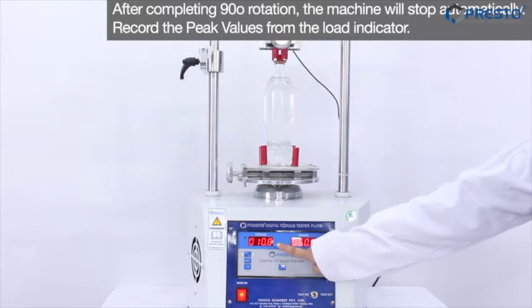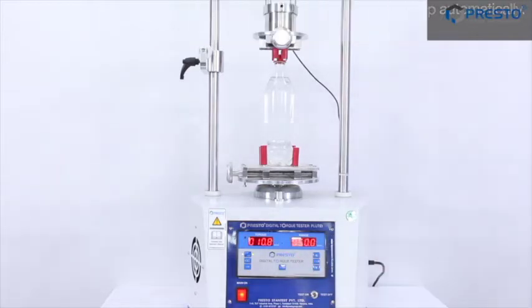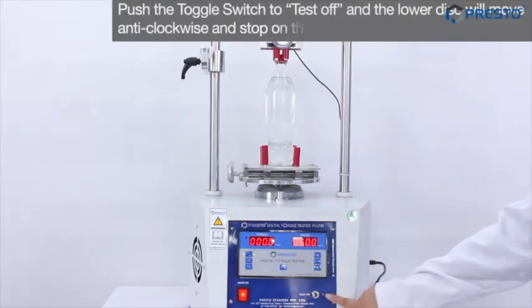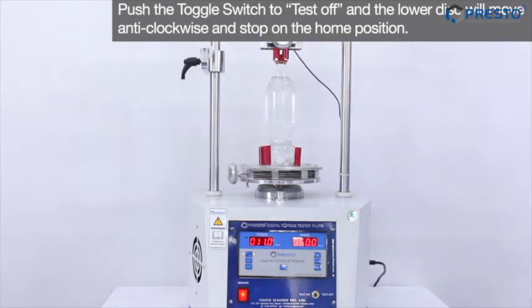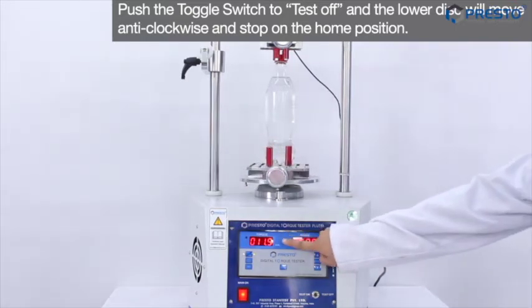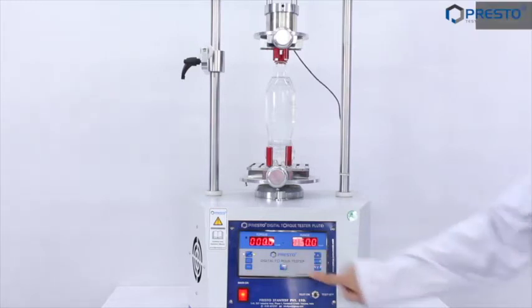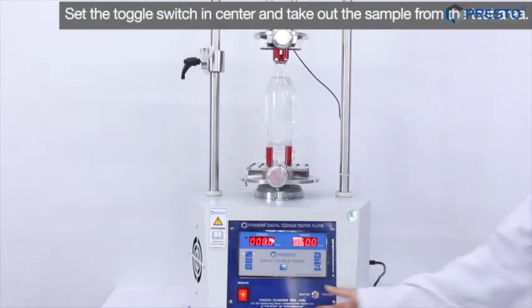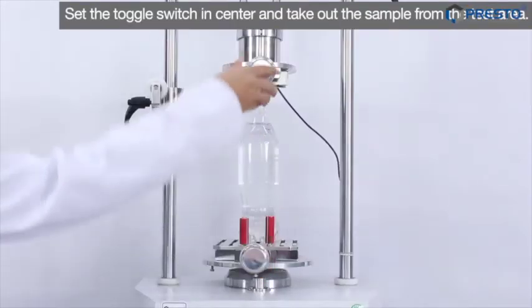Record the peak value from the load indicator. Now push the toggle switch to test off, and the lower disc will move anti-clockwise and stop on the home position. Set the toggle switch in center and take out the sample from the test area.